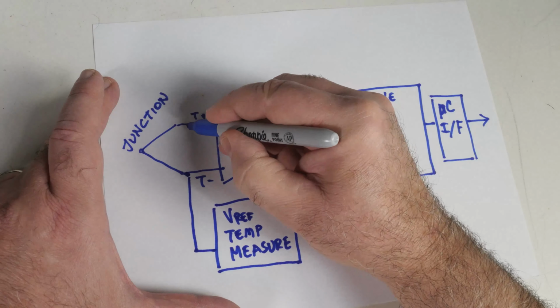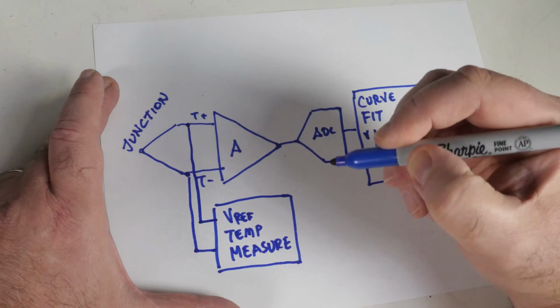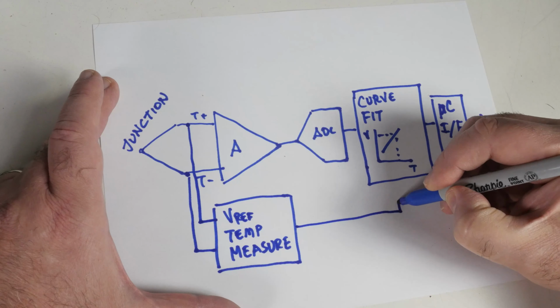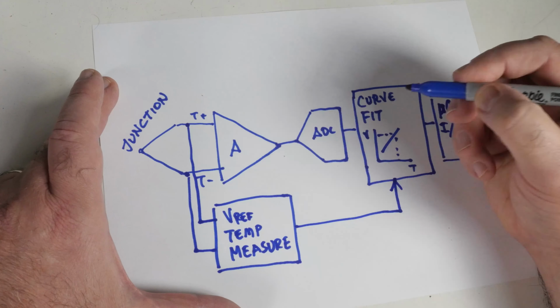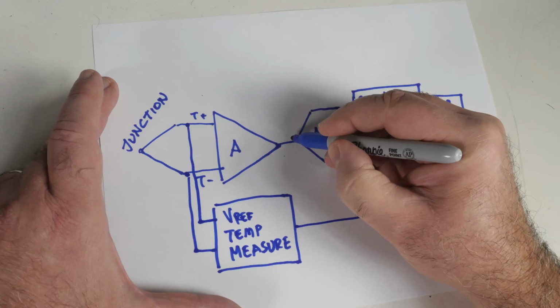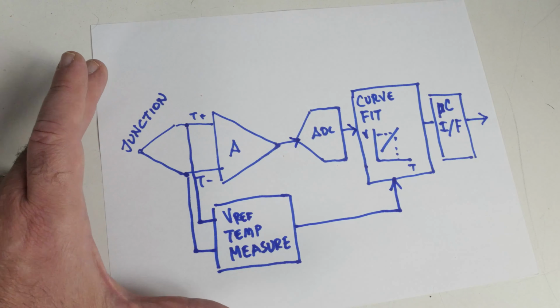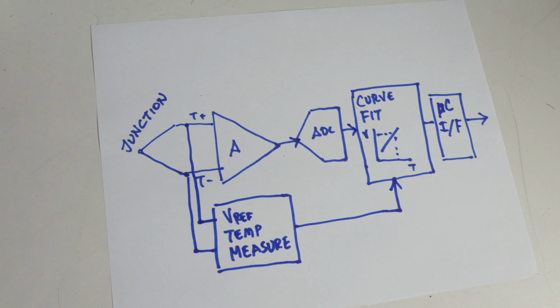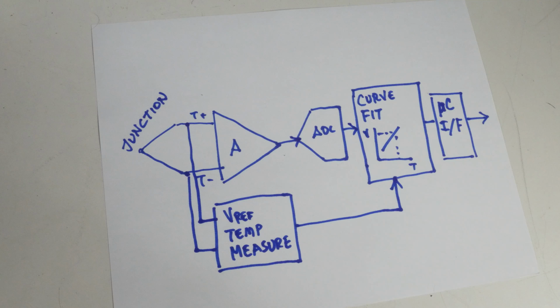To obtain the desired measurement, it is not sufficient to just measure the voltage across the wires. The calibration curves are provided for a reference temperature of 0°C. We will have to measure the reference temperature in our case and compensate for it if it's not at 0°C. This is normally done by measuring Vref with a temperature sensor such as a thermistor. The Vref is then used to compensate the voltage reading before applying the thermocouple curve. A thermistor is sufficiently accurate to do this measurement. Again, an amplification and accurate analog to digital conversion stage is required.